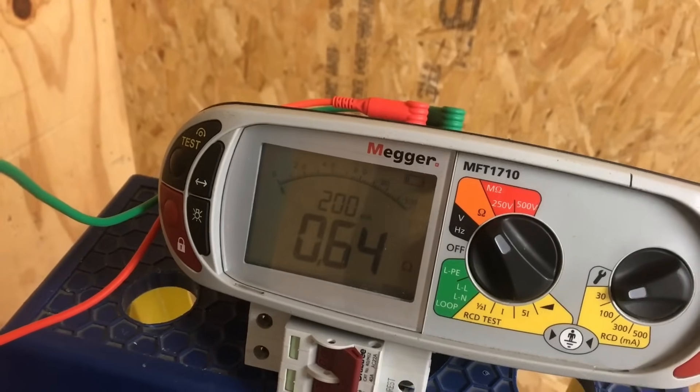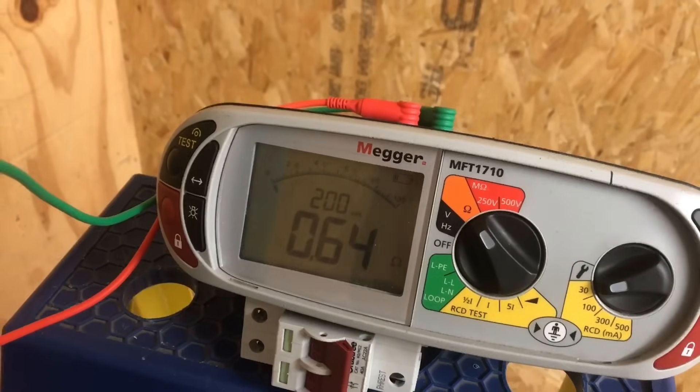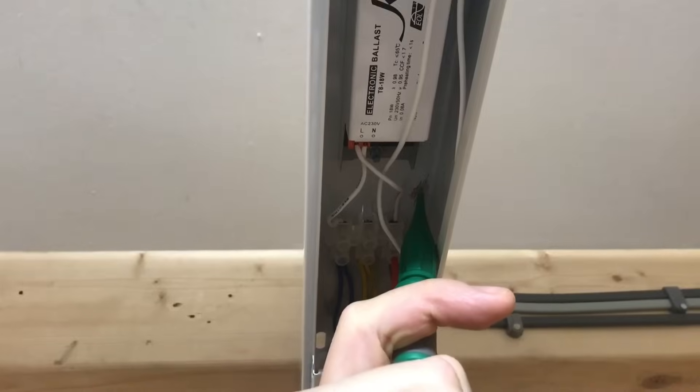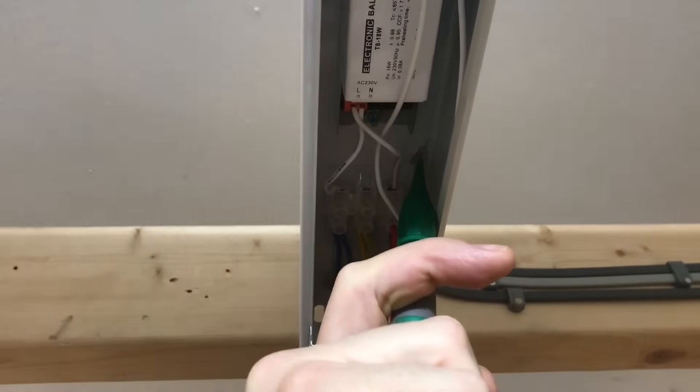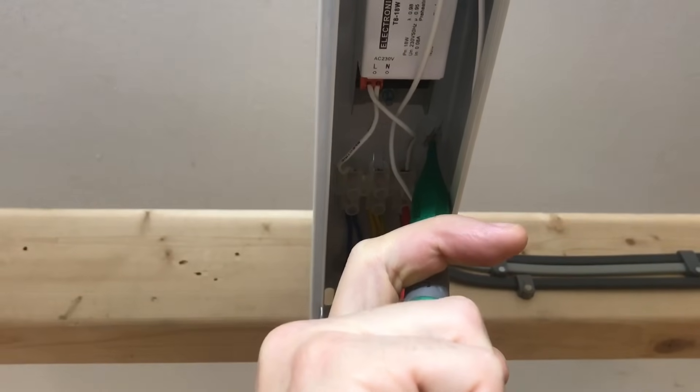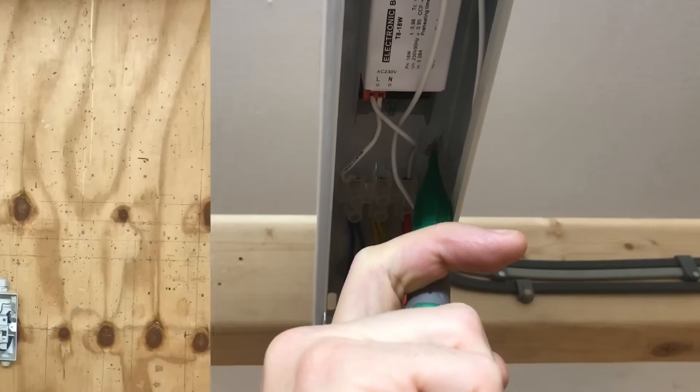We'll make a mental note of the value we took before - 0.64 ohms - and compare it to the value we got at the first switch, 0.18 ohms. The higher one is obviously 0.65, so that's the one we're going to keep in mind unless we get a higher reading. Let's move on and test the next light.